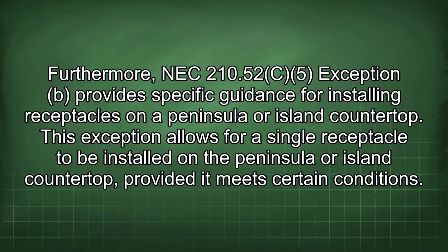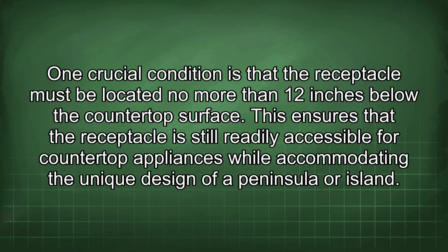Furthermore, NEC 210.52C5 Exception B provides specific guidance for installing receptacles on a peninsula or island countertop. This exception allows for a single receptacle to be installed on the peninsula or island countertop, provided it meets certain conditions. One crucial condition is that the receptacle must be located no more than 12 inches below the countertop surface.